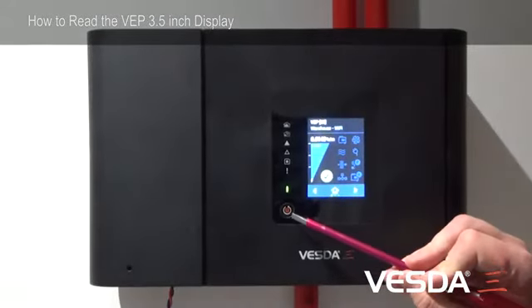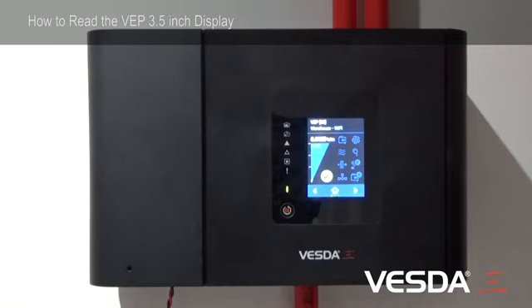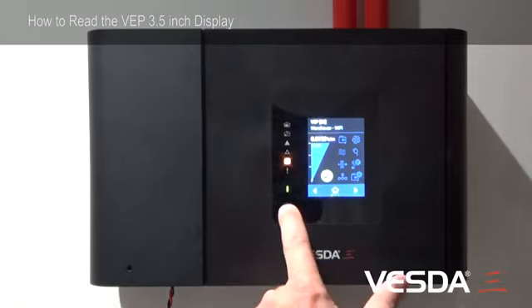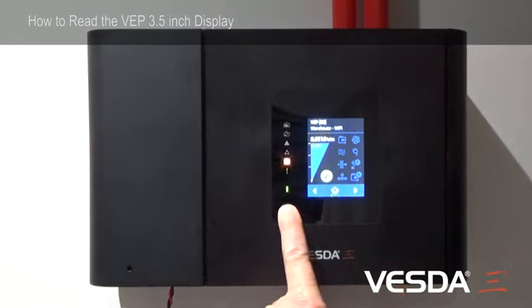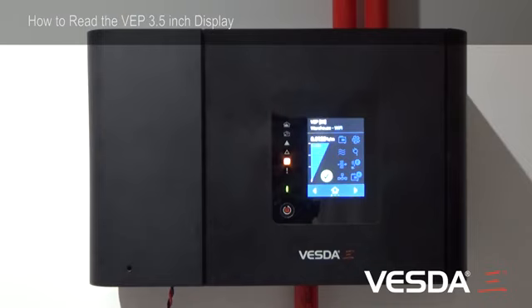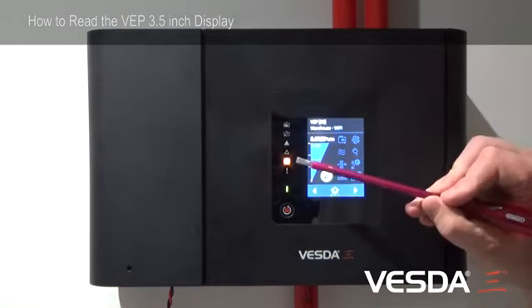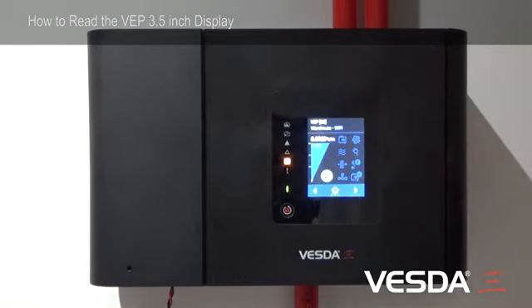The reset button on the bottom of the detector can also be used to disable or isolate the detector. Holding the button down for a period of approximately 4 seconds will allow the detector to be disabled. You can see how the disabled light has latched on, which indicates the detector is now in isolated mode. So any alarms generated will inhibit the activation of relays.